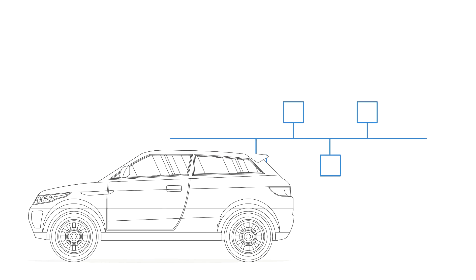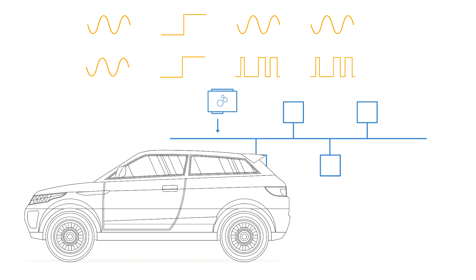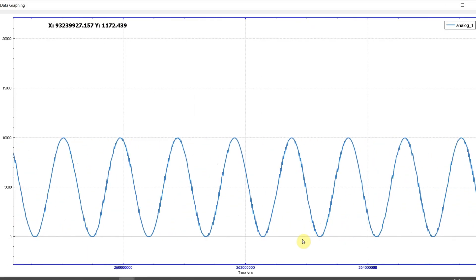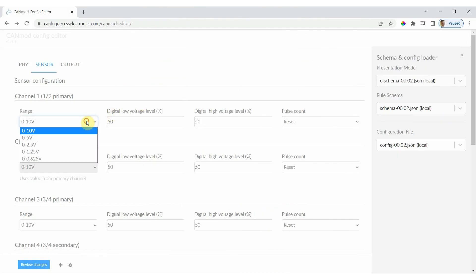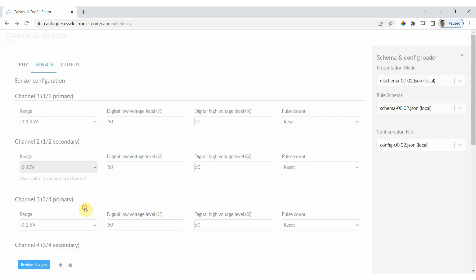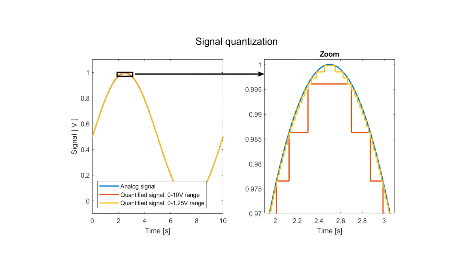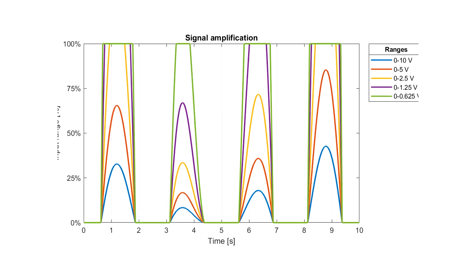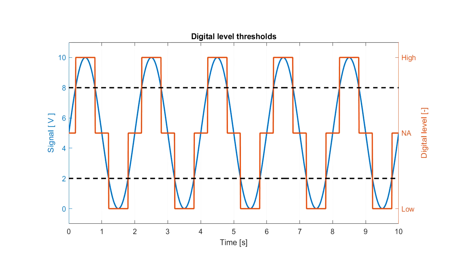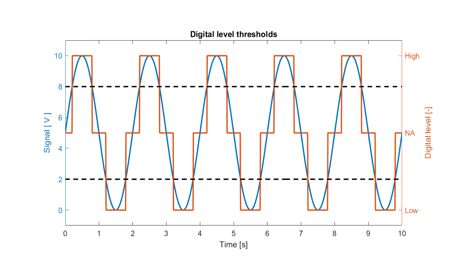Third, each input channel can be configured for analog, digital, or pulse measurements, meaning you can use a wide array of sensor types with the module. Specifically, the module performs analog measurements at a frequency of up to 1 kHz and a resolution of 10 bit. The input voltage range is configurable, with ranges spanning from 0 to 0.625 volts and 0 to 10 volts, allowing for optimal resolution and amplification. The module also performs digital input readings for each channel at a 1 kHz frequency with configurable low-high thresholds and optional hysteresis.